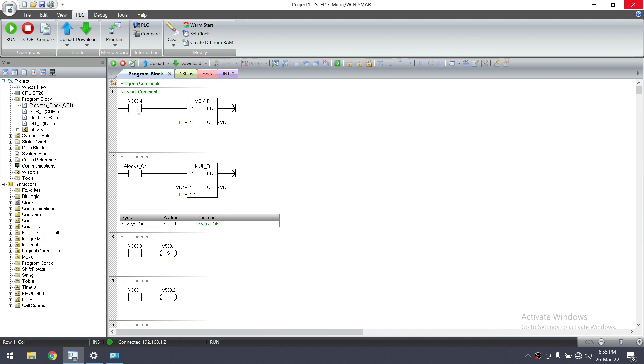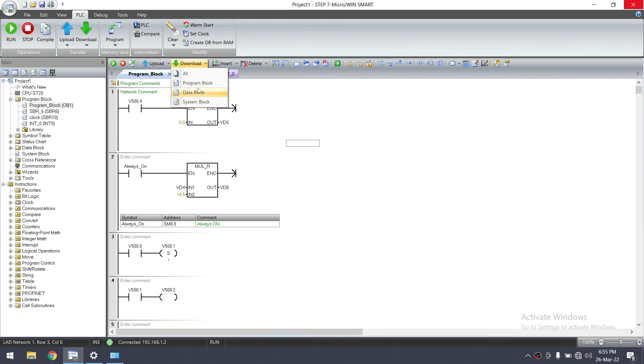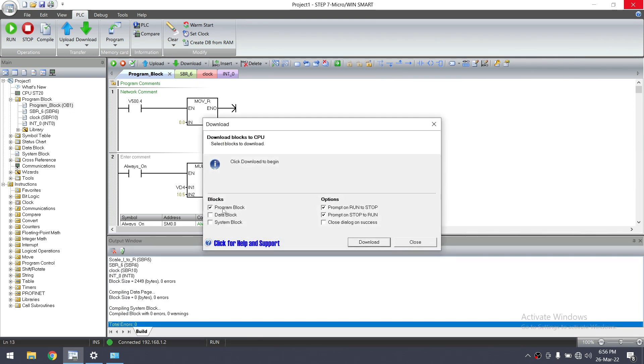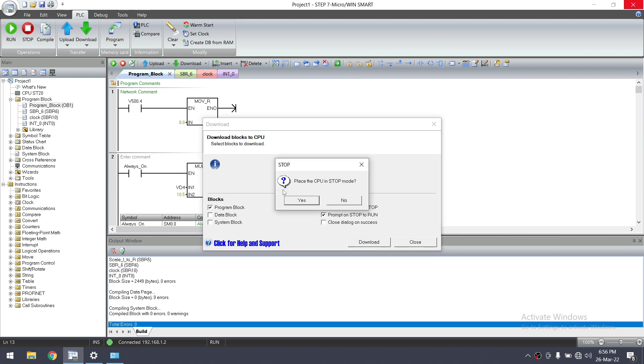To download this program back to the PLC, click Download. If you only want to download the Program Block, click on Program Block — this will keep all your values in retain mode. If you download all, all settings will reset to zero or default. Select Program Block only, then click Download. Confirm 'Place the CPU in Stop mode' — Yes.